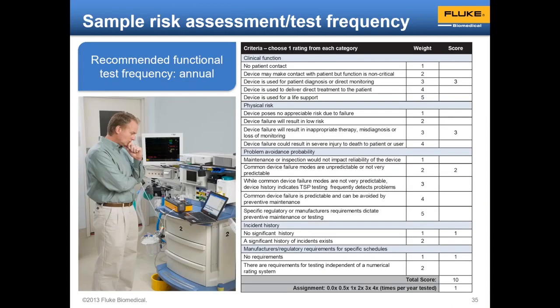So we do have a risk assessment for determining how often we should do the patient monitor testing that is included in this particular course about testing patient monitors. And there are 5 criteria that we use when we make that decision. Again, this is a decision that is made when we first do incoming inspection or acceptance testing of any medical device. We make the decision about how often we're going to test it. The manufacturer should provide that information to us in the brand and model specific service manual in the test procedure there. But a lot of times, especially in India and other parts of the world away from the US and Western Europe, the manufacturer does not provide that service manual or even the test procedure to you. And so you have to have some way to decide how often the testing ought to be done. This is the way that you do it.